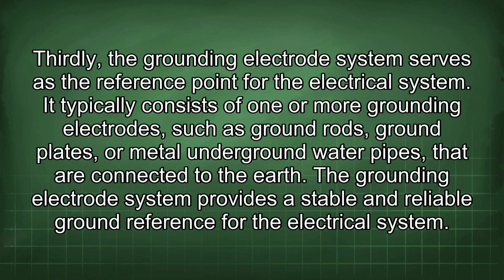Thirdly, the grounding electrode system serves as the reference point for the electrical system. It typically consists of 1 or more grounding electrodes, such as ground rods, ground plates, or metal underground water pipes that are connected to the earth. The grounding electrode system provides a stable and reliable ground reference for the electrical system.